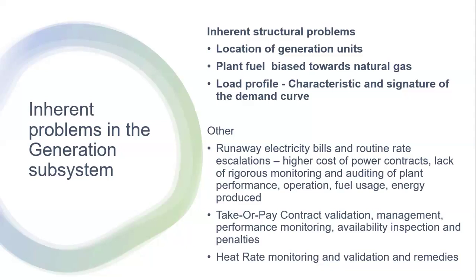Lower heat rate curves mean more efficient. So you have two units, one has a higher heat rate curve, one has a lower one. It serves me right to go with the lower heat rate curve one. And why is that important? Because it has a direct relationship with economic dispatch, right? That's where you differentiate the heat rate curves, MBTU versus power, then you get your incremental cost, dollar per megawatt hour versus power, and that's how you dispatch the generators. So it has direct cost and adequacy implications that need to be managed, monitored, inspected, and occasionally dealt with.